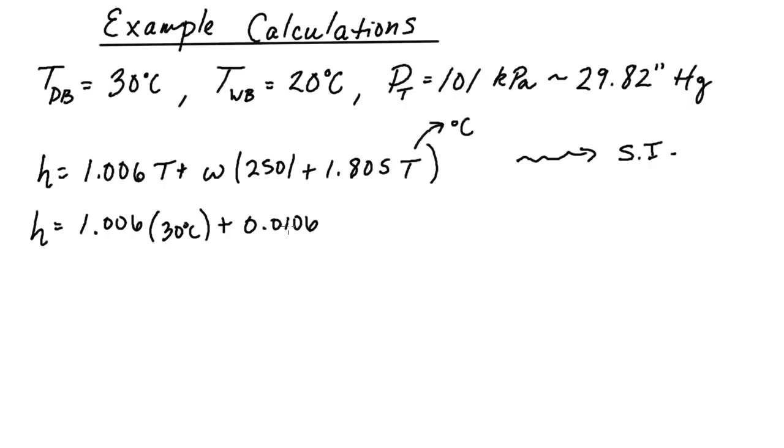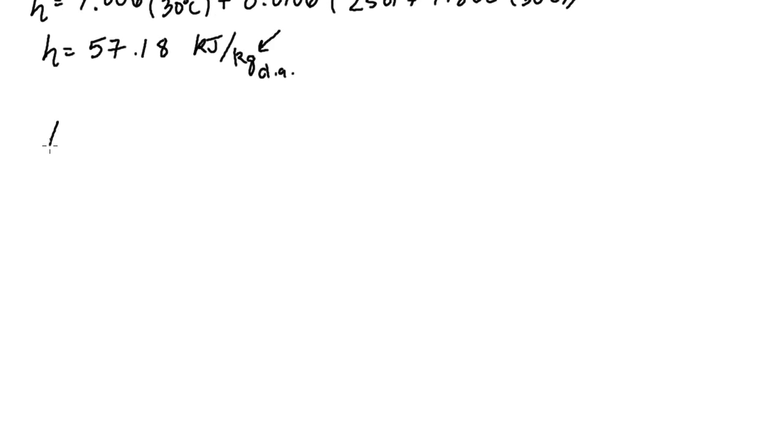And if I remember right, it was 0.0106 for a specific humidity. 2501 plus 1.805, also times 30 degrees C. And if you do that, you will get an enthalpy that is around 57.18 kilojoules per kilogram dry air. Remember, all these things that are normalized versus mass are going to be normalized versus the mass of the dry air. And the reason we do that is because in a typical HVAC process, the amount of dry air from the beginning to end does not change, while a lot of times we will add or take out moisture. We will humidify or dehumidify.